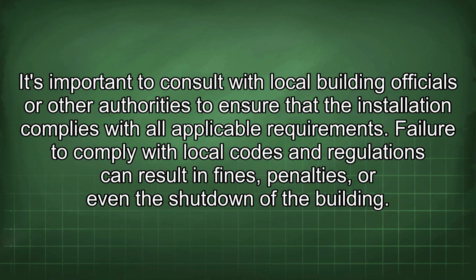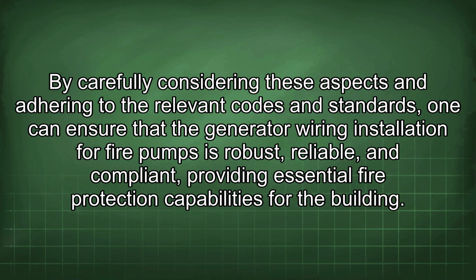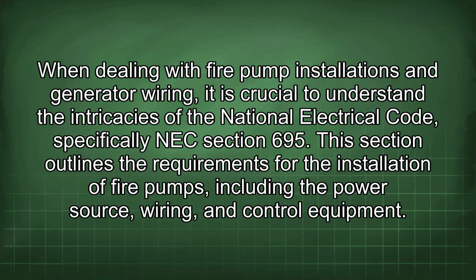By carefully considering these aspects and adhering to the relevant codes and standards, one can ensure that the generator wiring installation for fire pumps is robust, reliable, and compliant, providing essential fire protection capabilities for the building. When dealing with fire pump installations and generator wiring, it is crucial to understand the intricacies of the National Electrical Code, specifically NEC section 695. This section outlines the requirements for the installation of fire pumps, including the power source, wiring, and control equipment.